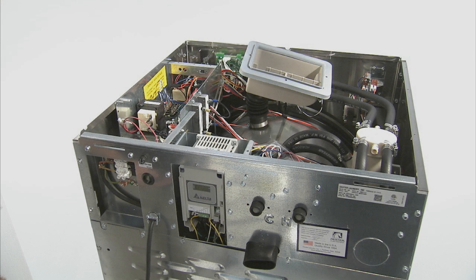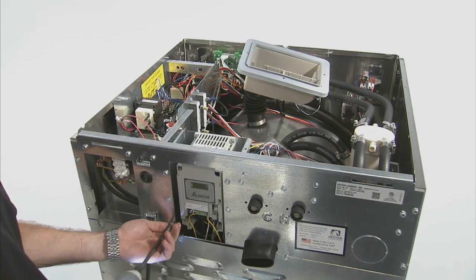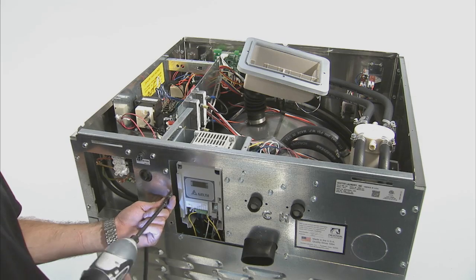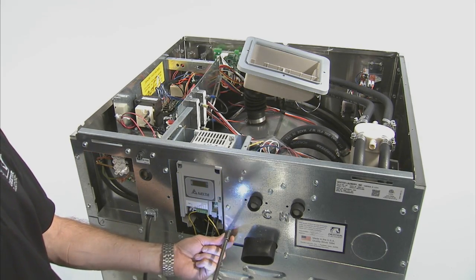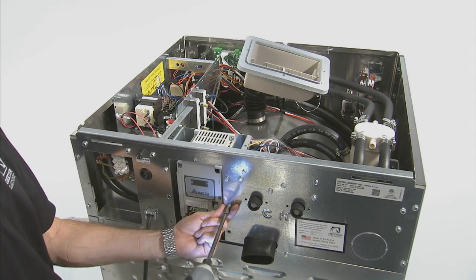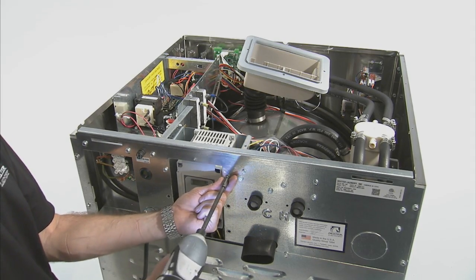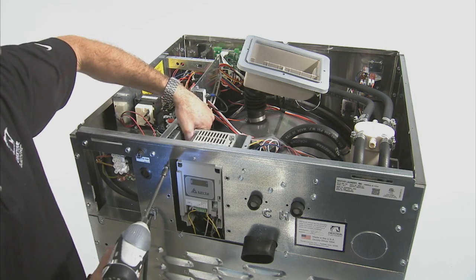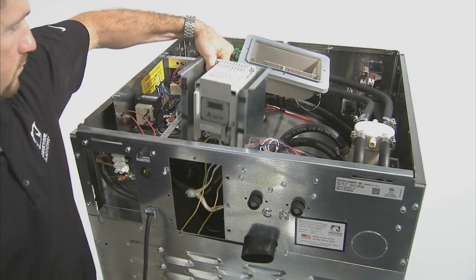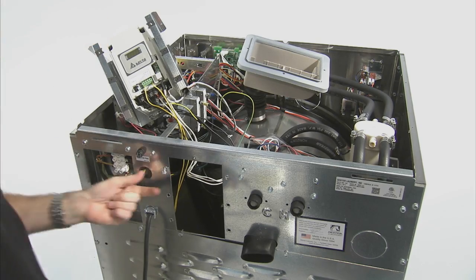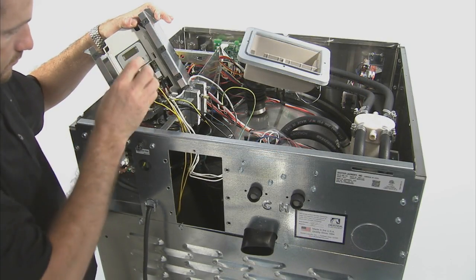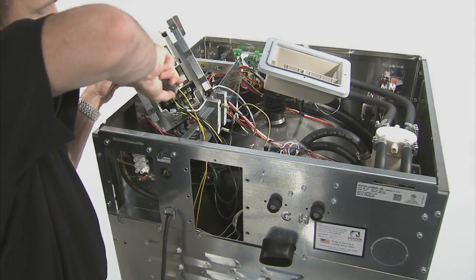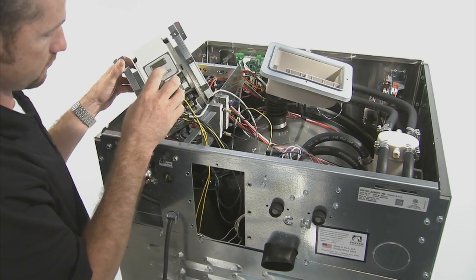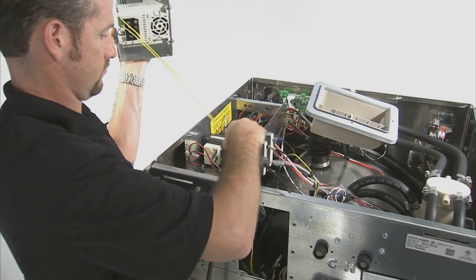install the replacement VFD. If the VFD display is blank, non-illuminated, or has 8888 displayed, these are signs of a failed VFD. The VFD will need to be replaced. To remove the old VFD, loosen and remove the 6 5/16 screws securing the VFD to the machine. Next, pull the VFD out of the mounting bracket to disconnect the wiring. Before removing any wires from the VFD, take a photo or write down the wire locations to use as a reference when installing the new VFD. Then, remove the old VFD.